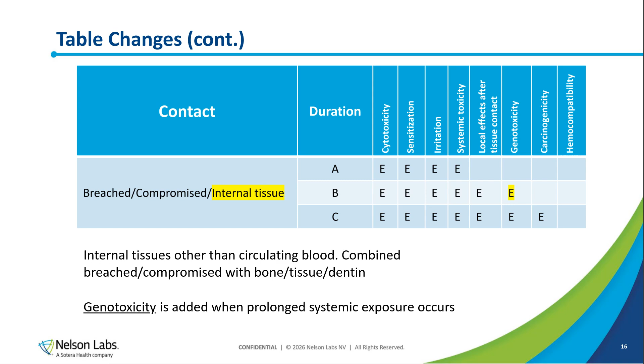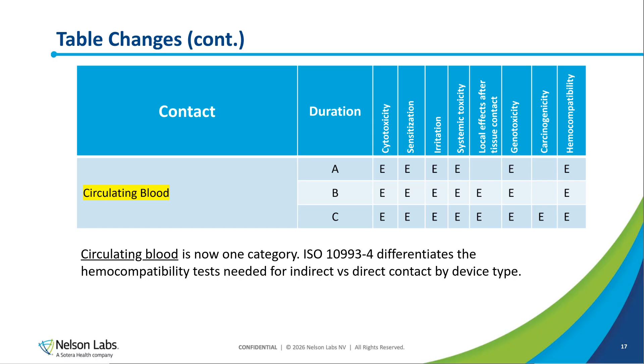We now have one big family of devices that contact blood. It's one category. And if you want to understand which biological effects apply, which hemocompatibility tests you need to look at for your device, you really need to look into ISO 10993-4, to see also a difference of considerations between indirect versus direct contact with blood for each of those devices that do contact blood.